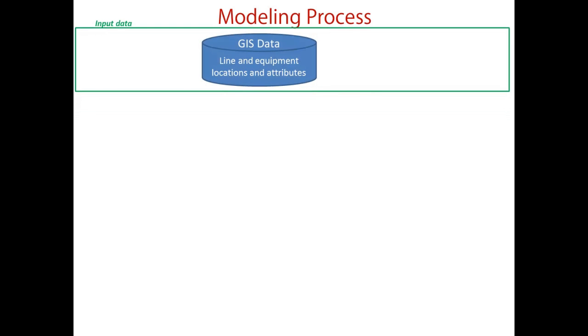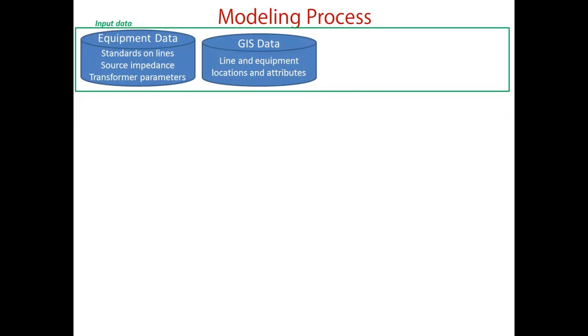Here I present an overview of the modeling process. The first step in modeling is to gather the very extensive GIS data available. So the GIS has the information on all the line and equipment in the feeder, and it has the basic location information, the IDs, and all the physical attributes. And for each of the line and equipment listed in the GIS, we need to collect all the electrical characteristics, like the line type, the conductors, the number of strands, and so on, which come from various standards. For transformers, for example, we need the impedances, the X/R ratios, and so on. So the electrical data for all the equipment needs to be collected.